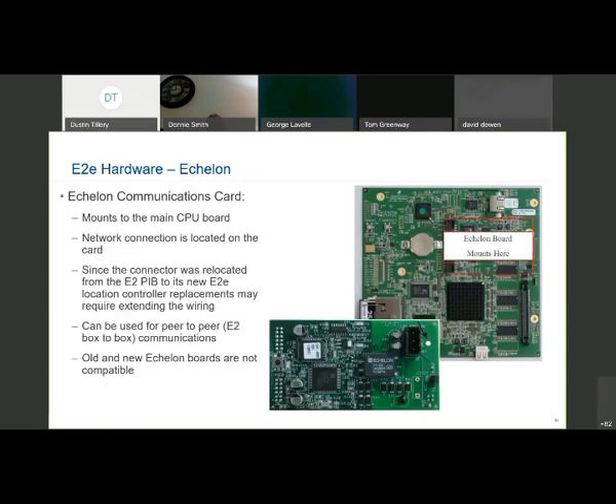All right, the Echelon card. Again, like I said earlier, the old E2 came with it standard. With the new E2, you have to have a new card, which means a new part number for you guys. It does mount to the back of the CPU board. It handles network communications for that Echelon network, peer-to-peer communications from E2 to E2, or the old style of air handling and RTU communication was done through Echelon as well.